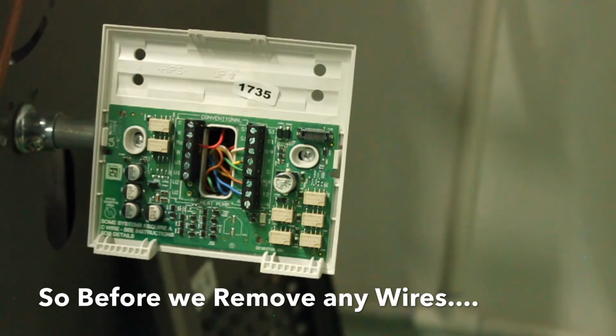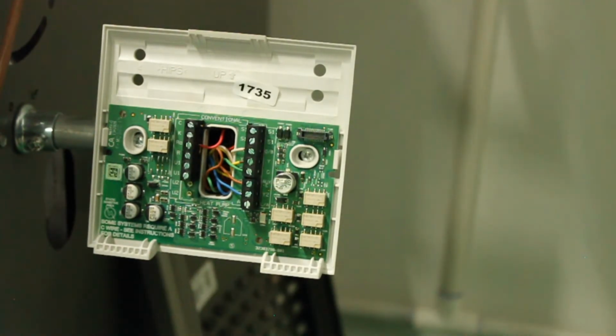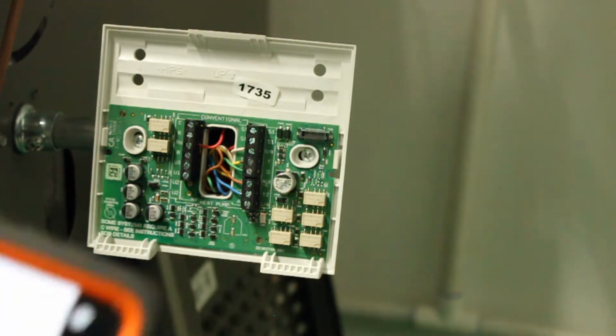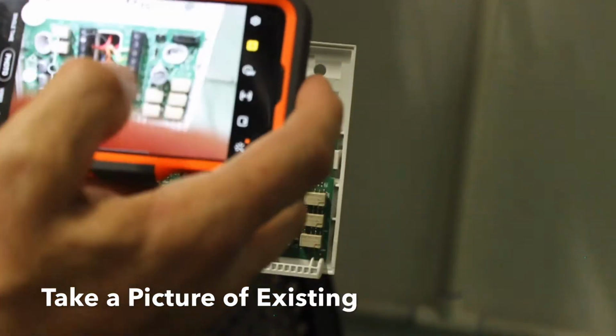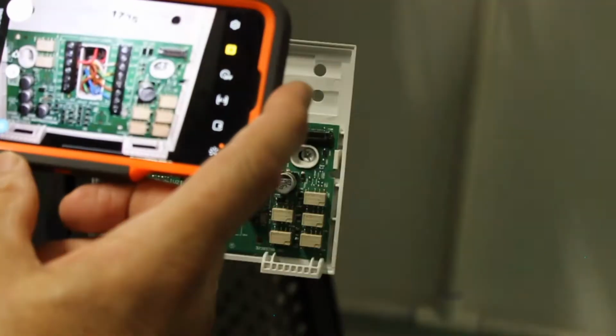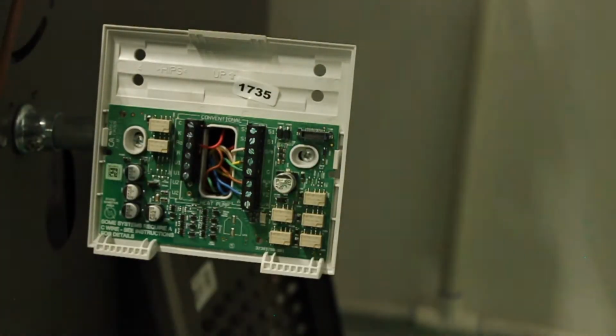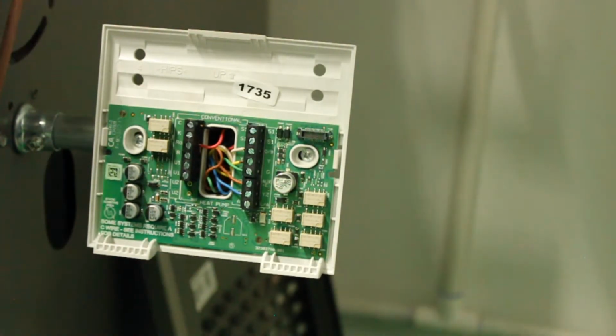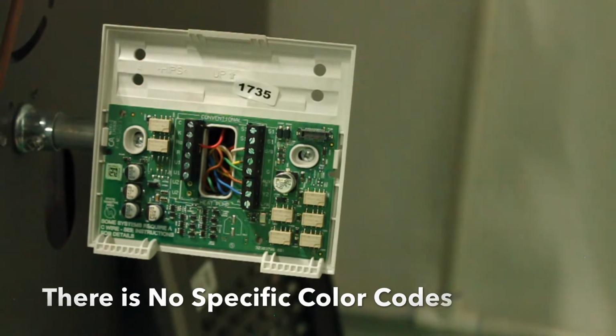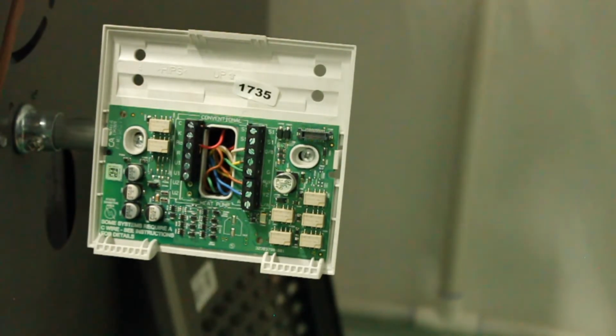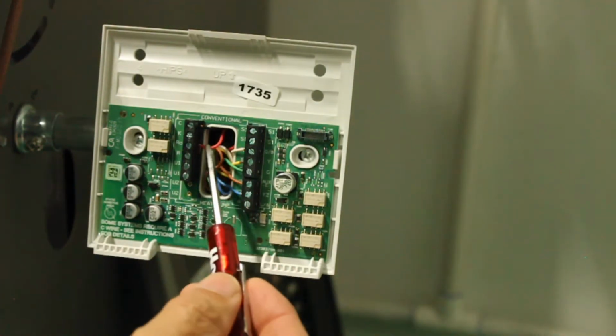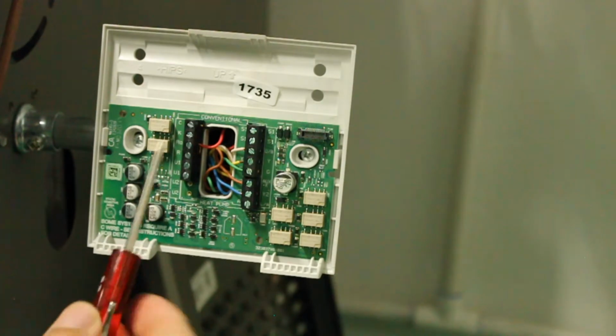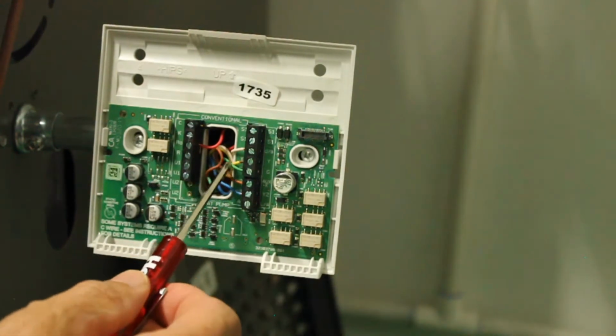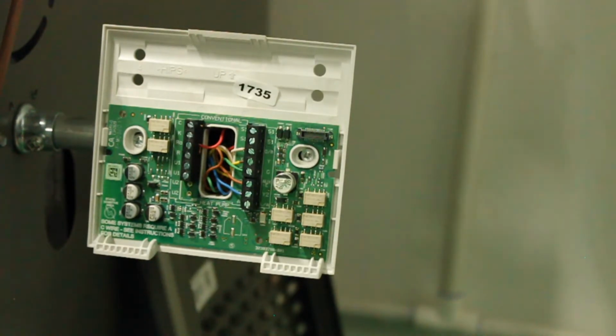So before we take any wires off, if we were to take them off, I'm going to get my phone here, and you want to document as much as you possibly can. And so you want to actually take a picture of the wires before you disconnect any to come off the wall. Now in color codes, there's no specific color codes, but in the trade, we kind of give ourselves our own color codes. So right now we have a black, a red, that's on my left side. And then the other side, we have the white, the yellow, the green, the brown, and the blue, which is 5 wires. So there are 7 wires that actually connect to this thermostat.